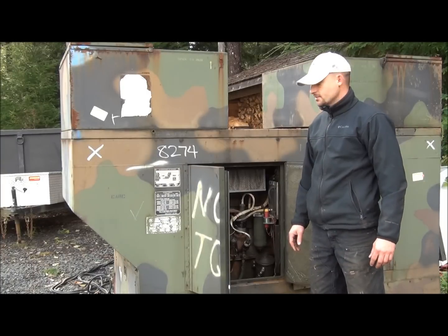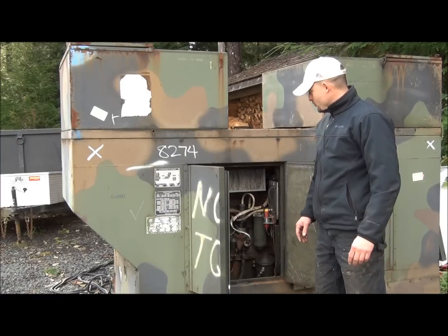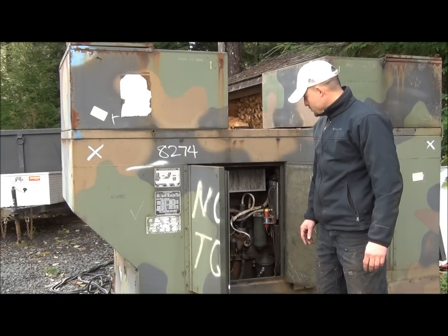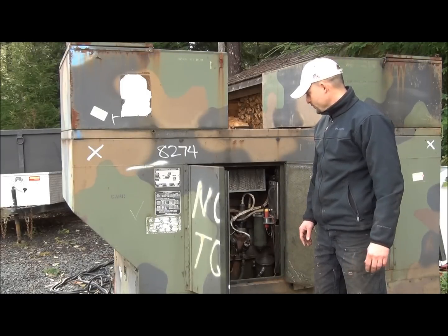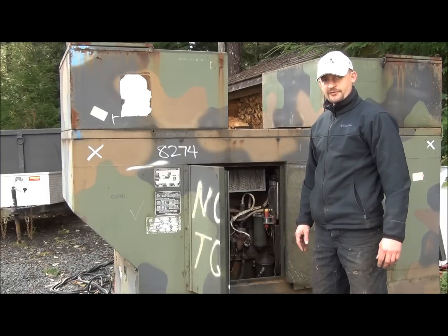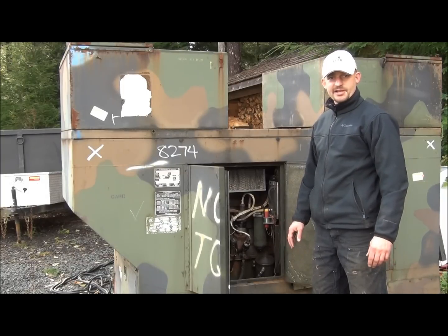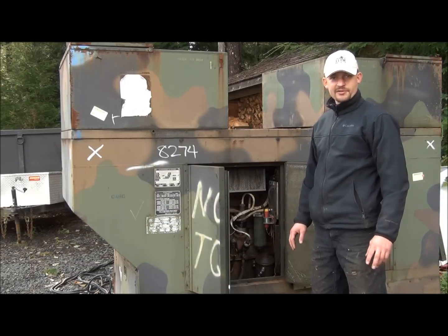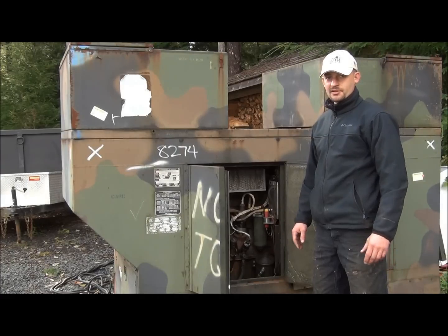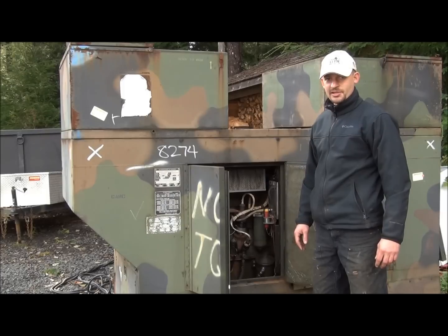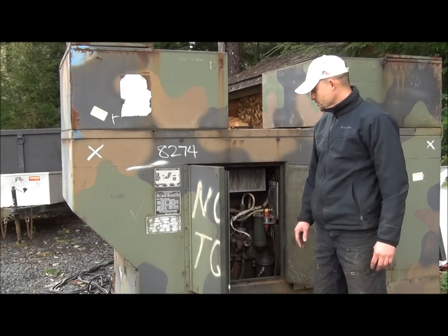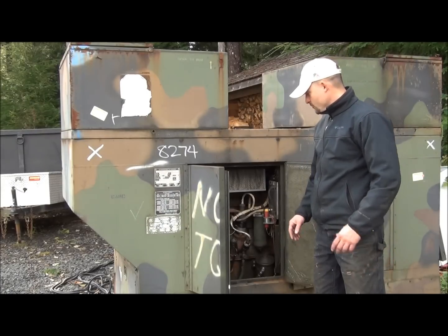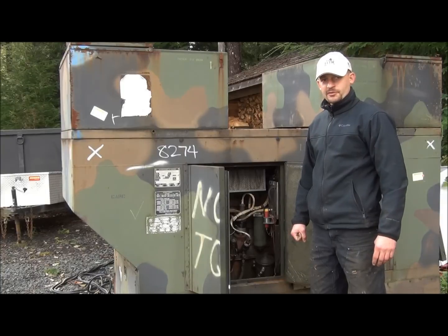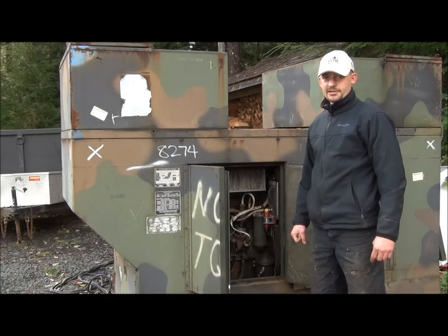There's no leaks, nothing showing up for any of the cooling system, fuel system, oil, and everything. I went ahead and checked the oil level, and it doesn't appear to be contaminated by anything. It's nice and clean. There's no evidence of any water. The level hasn't risen at all, so I'm fairly certain it's not pumping any diesel into the oil system. And everything seems to be running pretty good, so hopefully we'll get this over voltage problem sorted out, and then we can continue with the testing.